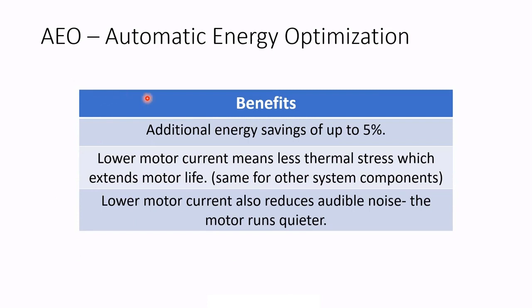The benefits of that are energy savings — up to an additional 5%. That lower motor current means less thermal stress, which extends the motor life. The same is true for other components like the drive. Anything that's carrying less current is going to last longer. Another nice added benefit is that lower current is going to reduce audible noise — the motor is going to run quieter.